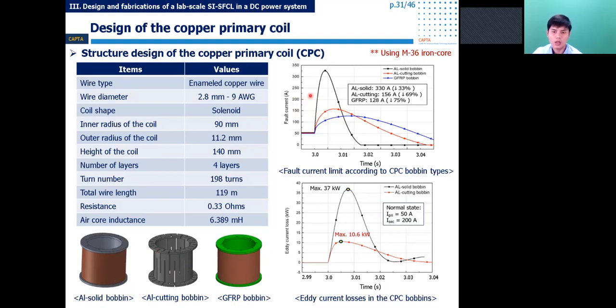Here shows the fault limit performance of the SFCL according to the primary bobbin type. The higher eddy current loss of the aluminum solid bobbin significantly reduces the fault limit ability of the SFCL. In case of the GFRP bobbin, there was no eddy current loss, so the fault limitation, you can see, is very good. However, the GFRP material has a very high cost compared with the aluminum. Therefore, I suggested using the aluminum cutting bobbin to reduce the eddy current loss as well as the material cost of the primary bobbin.